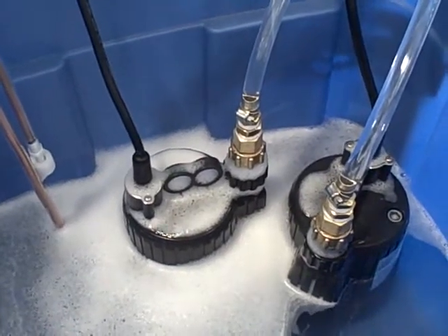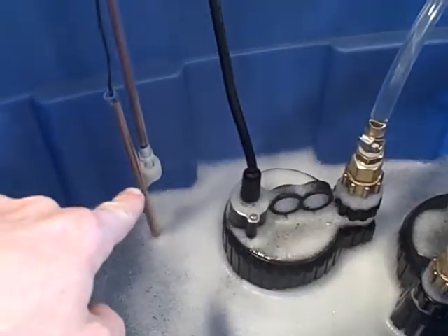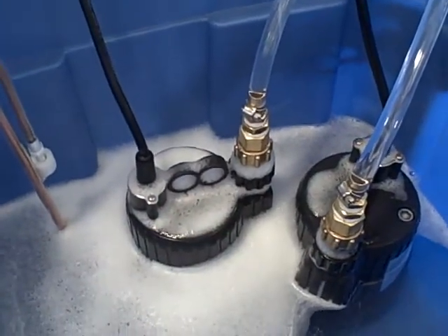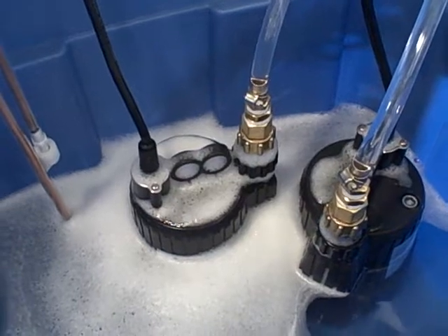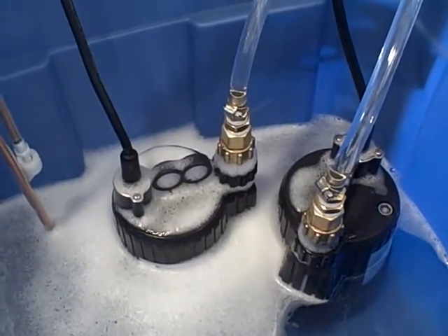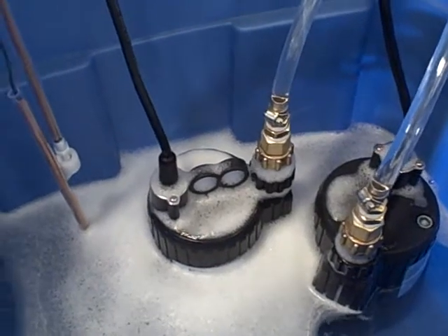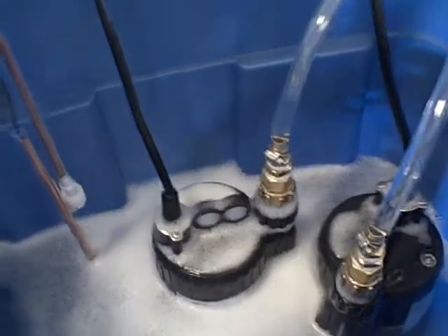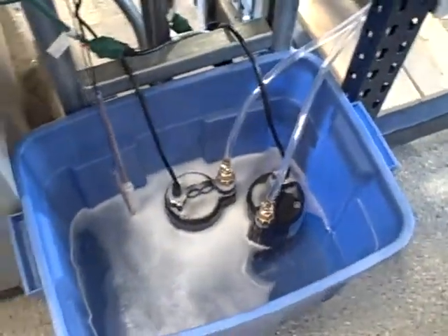And what the PLC does is when it senses a high water level, it decides which pump it's going to turn on based on the one that's run the least amount of time. So the PLC maintains a pair of retentive timers that's measuring the on time of each pump. And on the next start cycle, it looks at which pump has run the least, and it runs that one. So effectively, it alternates the pumps back and forth.